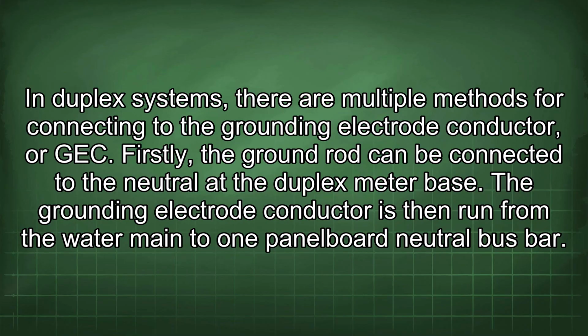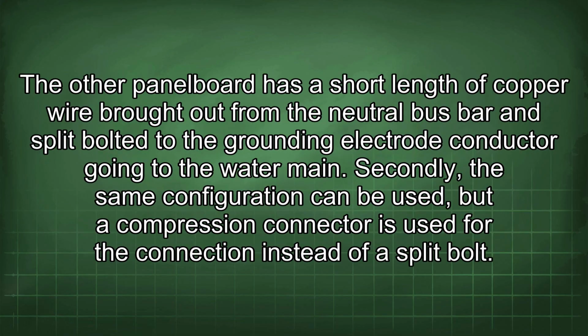In duplex systems, there are multiple methods for connecting to the grounding electrode conductor, or GEC. Firstly, the ground rod can be connected to the neutral at the duplex meter base. The grounding electrode conductor is then run from the water main to one panelboard neutral bus bar. The other panelboard has a short length of copper wire brought out from the neutral bus bar and split bolted to the grounding electrode conductor going to the water main.